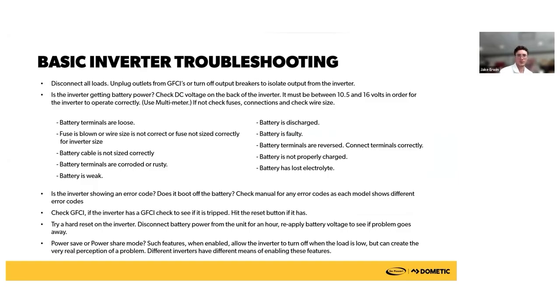A lot of inverter issues are actually battery issues, either a bad fuse or poor connections. Could be load issues. That's usually a poor connection thing, or maybe the battery's bad, or in the case of a lot of newer lithium batteries, maybe the BMS has just shut the battery off to protect itself. So always start at the basics.